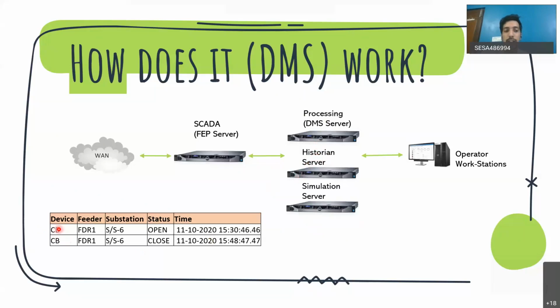Suppose there is a circuit breaker connected to a particular feeder in a particular substation, and it got tripped at a particular moment in time. The fault was found and rectified immediately, and later the breaker was closed at some other point in time. What the historian server will do is store when it was opened, along with the timestamp, in a database, and when it's closed, that information is also stored along with its timestamp.